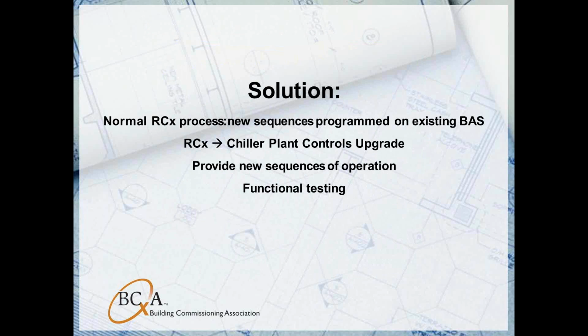Since our most pressing issue to solve was our chiller plant, what are our options here? We could modify our existing Niagara BAS programming. That would be option 1. We could keep the Niagara BAS, but gut the programming and start from scratch. But that doesn't solve the problem that we would still not have the campus standard as our front end. So a third option is to upgrade the chiller plant controllers to Johnson Controls NAE controllers and then reprogram the entire chilled water plant.